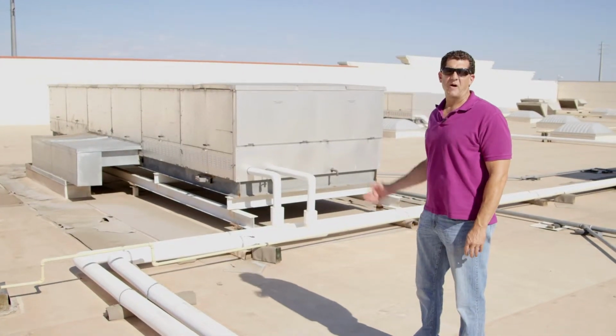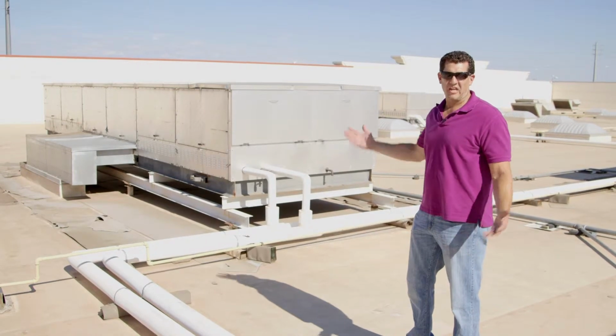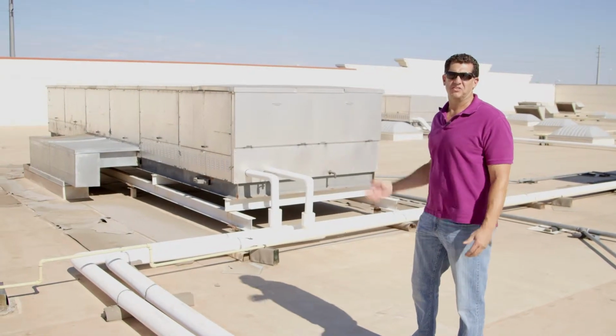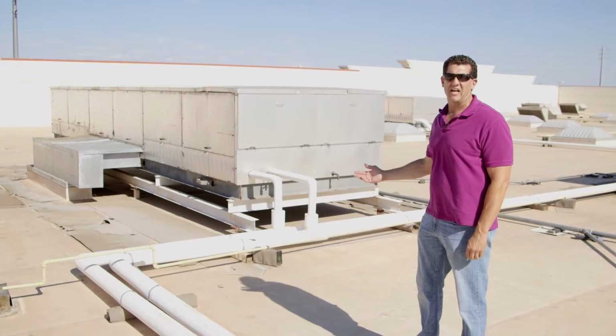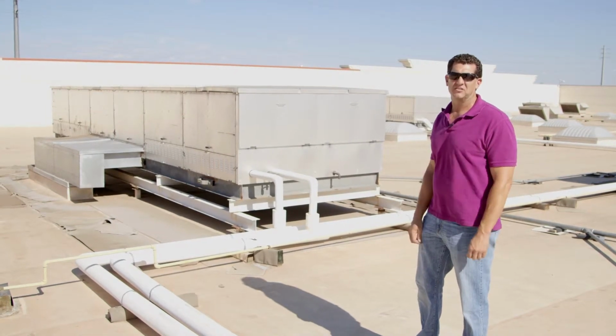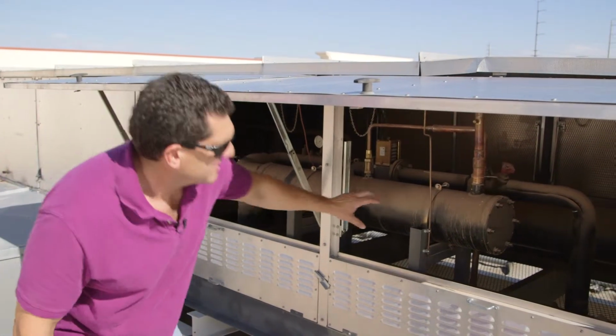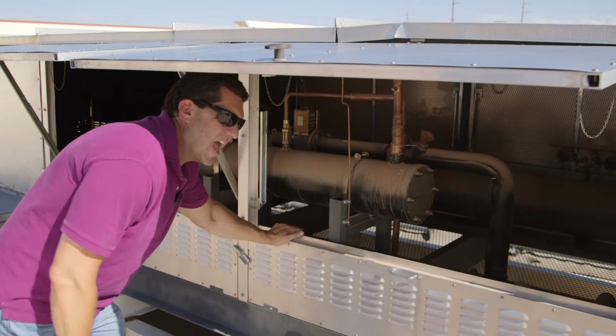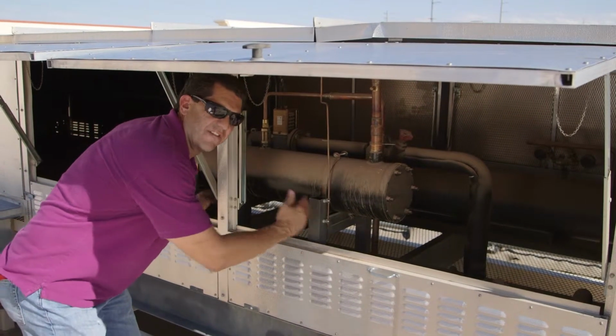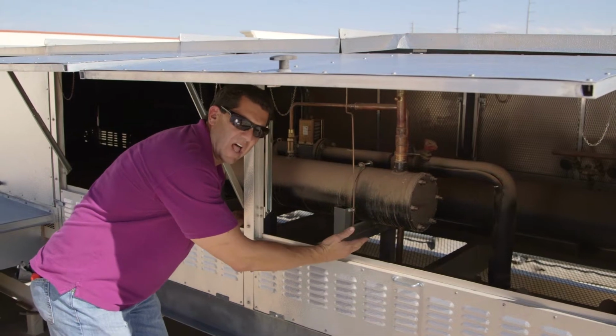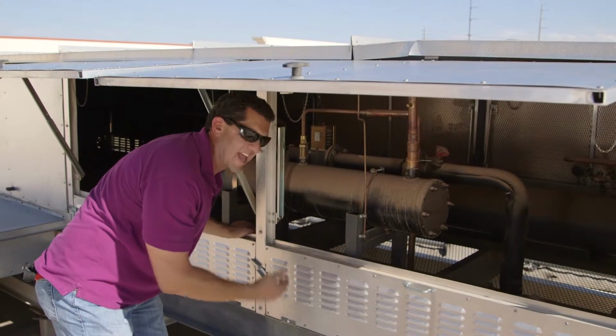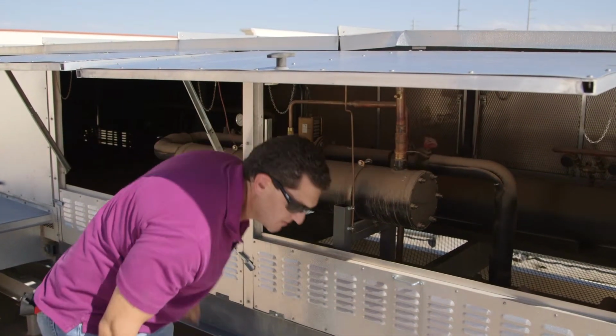So we're up on the roof by the rack house where you can get your discharge pressures, but this is also where there's another potential dead leg. I'm going to show you where that dead leg is. So we opened up the panel. Inside here's your heat exchanger, and in every rack house there's about a 7-foot dead leg that comes off the supply line. So we're going to flush that, and that should be done every service.